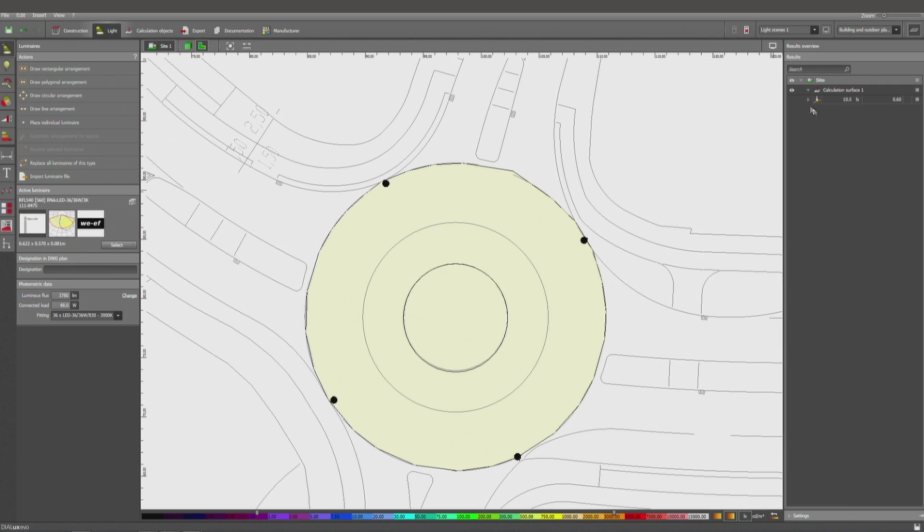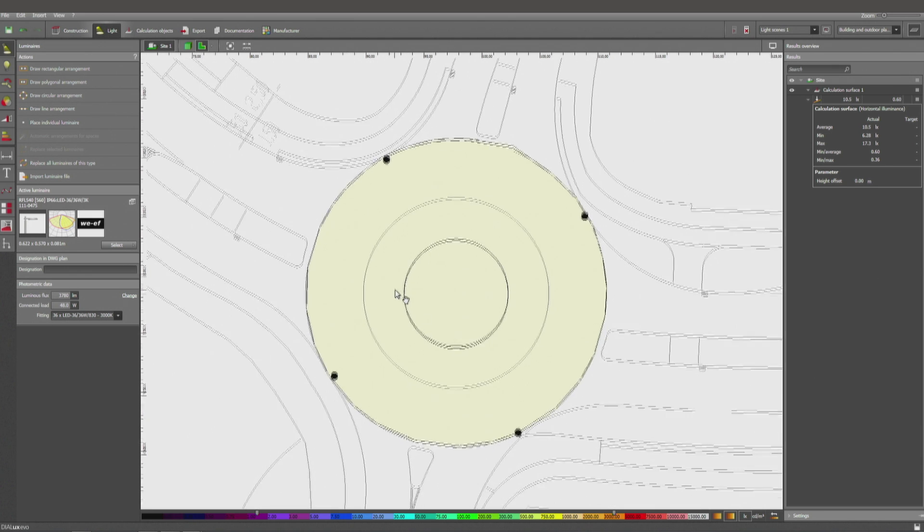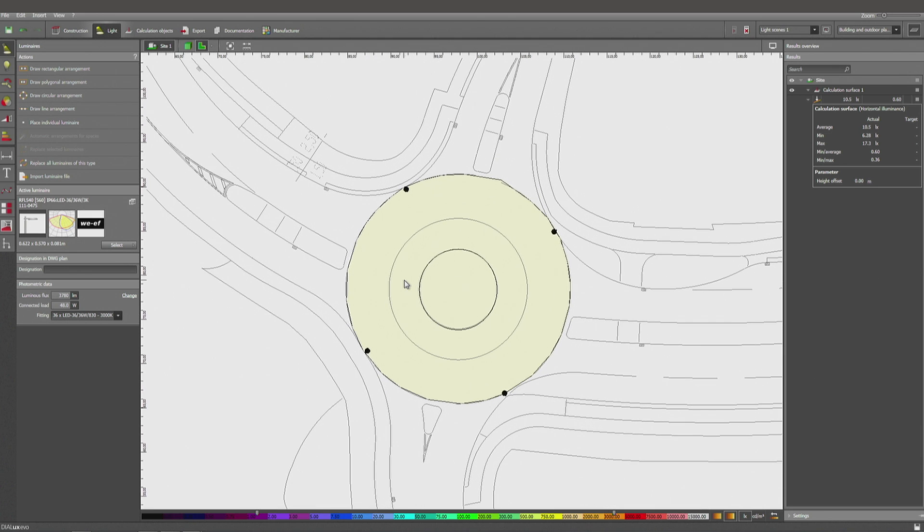So the average now is 10.5 lux, a min of 6.7. We can verify the min and average ratio here in these places, which should be enough to check if that surface is going to meet the requests by EN 13201.